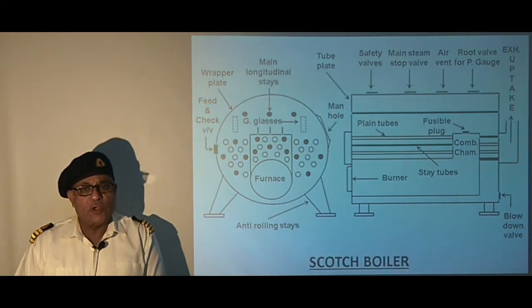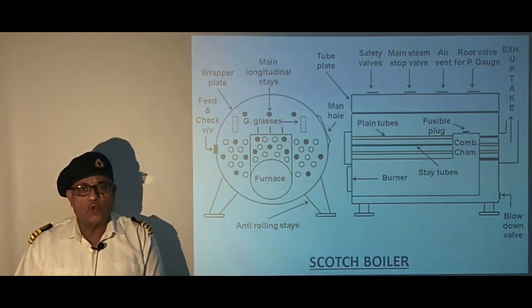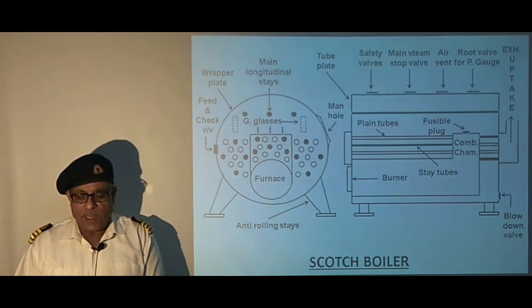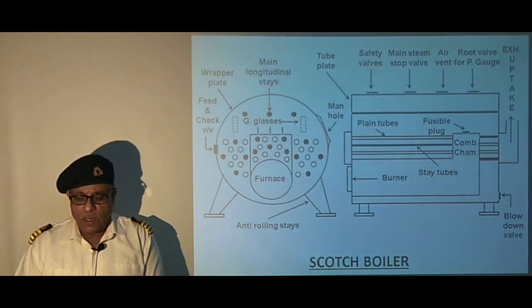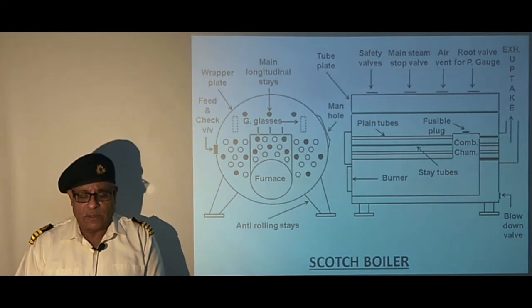Plain tubes and stay tubes are in the ratio of 3 to 1. These tubes carry flue gases from the combustion chamber to the boiler uptake and support the boiler front tube plate and combustion chamber front plate.